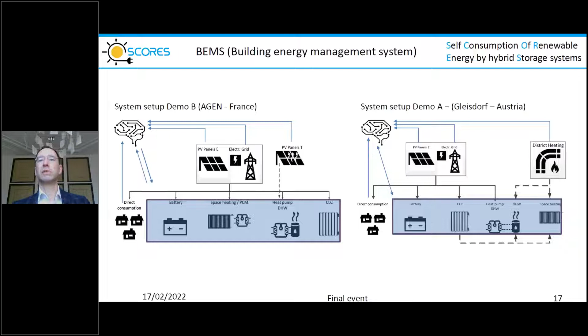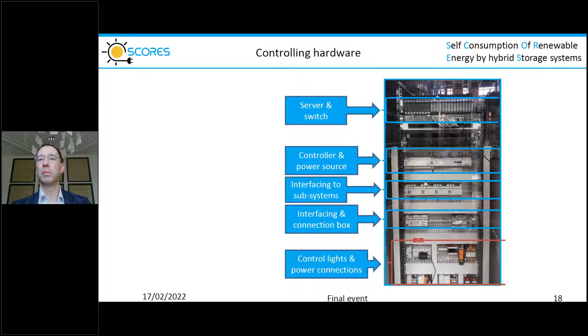The system we've built consists of a server where the algorithms run, where the logging is done, and where the weather API comes in, some communication components, the controller that executes all the commands set up by the BEMS, some interfacing equipment, and some auxiliary equipment to make it all work, like power supply. On the server, two algorithms are running: one prediction algorithm and one decision algorithm.